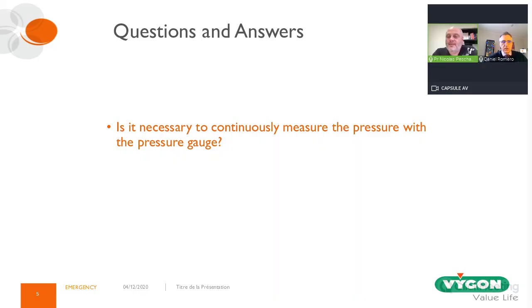Thank you. Next one: is it necessary to... No, actually, when you put on the device, you just have to check. There is a green part on the gauge, and you just have to set the flow to obtain the good positive pressure that you need. Usually it's between 7 and 10, regarding the objective of SpO2 you want, and once you're still in the green, you can leave the device on, because as it's an open flow device, you don't have to set your pressure again. The pressure will stay the same.